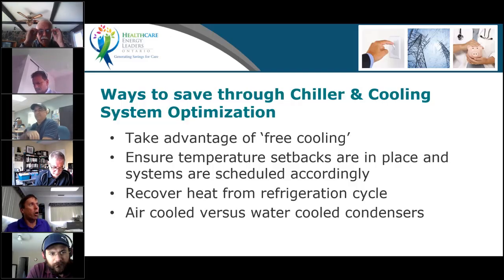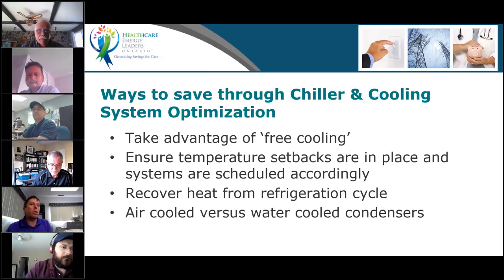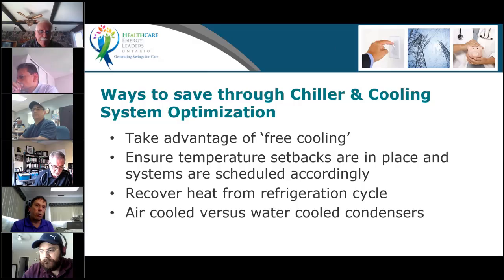If you've got a heat recovery chiller, free cooling will rob you of heat recovery capability. So most of the time, if you have a heat recovery chiller and it's worth running it, and I insist, is it worth running the heat recovery chiller, then you don't want to unload that chiller. You want to keep it loaded so that you can recover that internal heat, that generated heat from inside your building, to heat the perimeter of the building and to heat the fresh air coming into the building using that recovered heat.